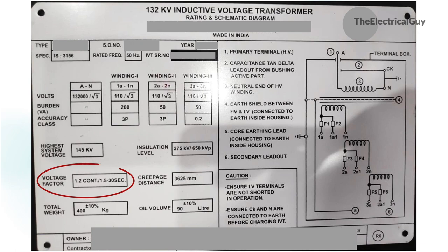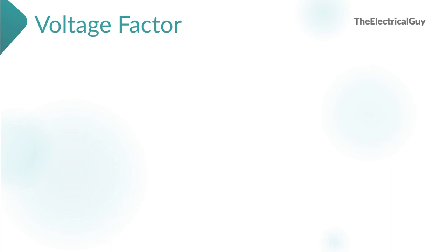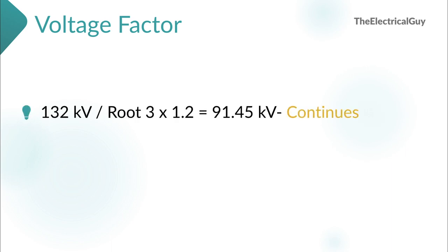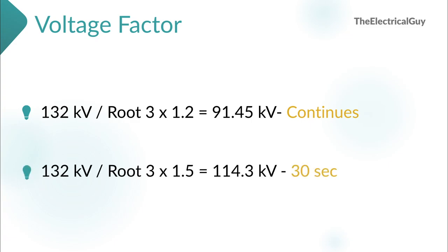The next parameter is voltage factor. On the nameplate it is mentioned as 1.2 continuous and 1.5 for 30 seconds. 1.2 continuous means the IVT is capable of sustaining 132kV/root 3 multiplied by 1.2 — that is 91.45kV — continuously. In normal conditions, only 132kV/root 3, approximately 76kV, will flow. But the IVT can handle 91.45kV continuously. 1.5 for 30 seconds means the IVT can take 132kV/root 3 multiplied by 1.5 — that is 114.3kV — for 30 seconds. Voltage factor is important during abnormal system conditions which may cause high transient voltage or voltage swell.